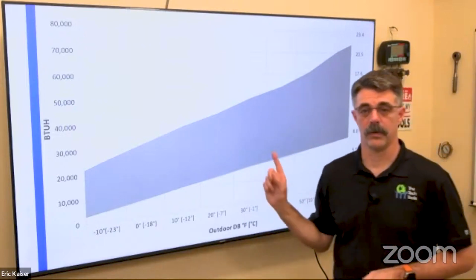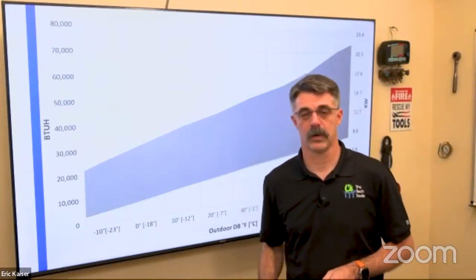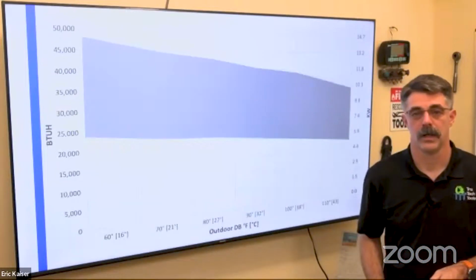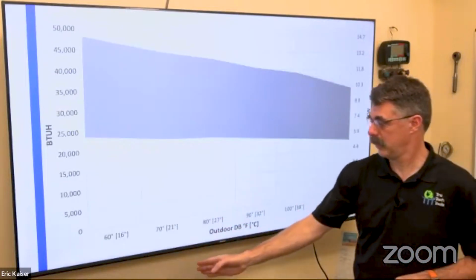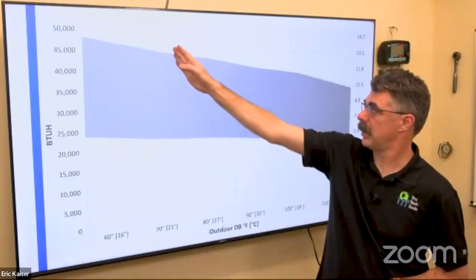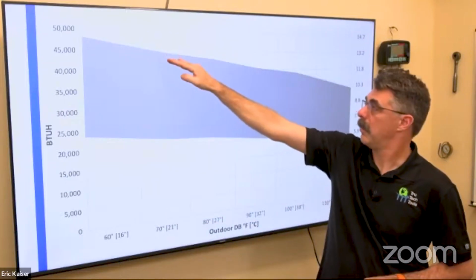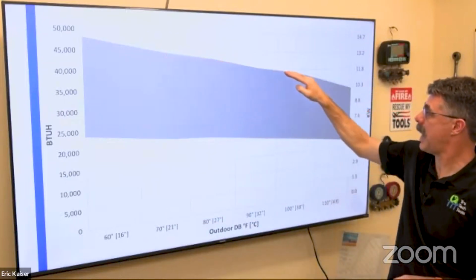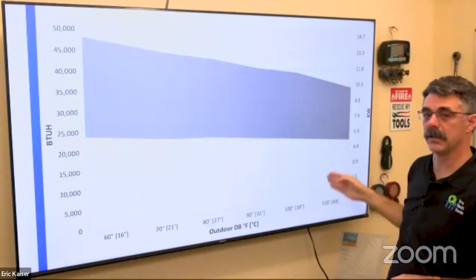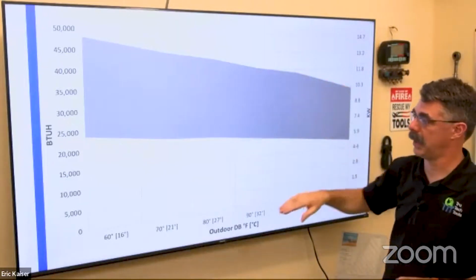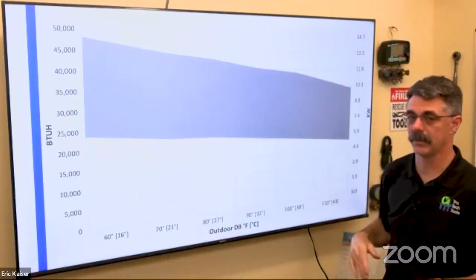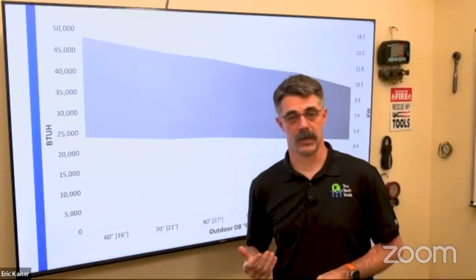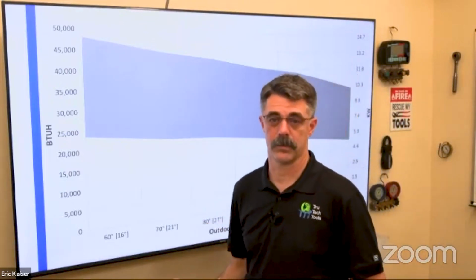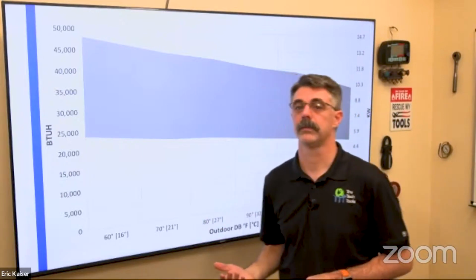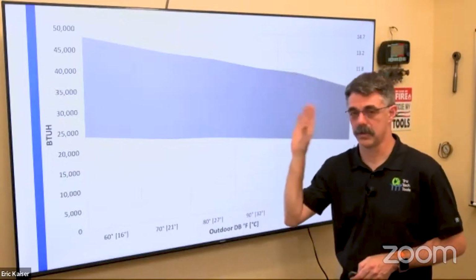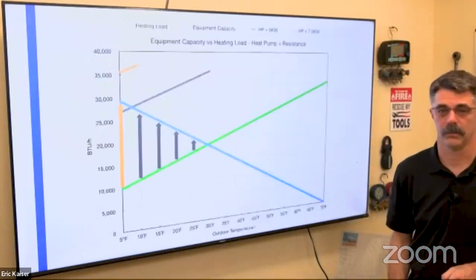And just so you know, this happens to be the heating performance curve of a unit, right? It does the exact same thing in cooling. You'll see this is 70 degrees right here. My maximum tapers off the hotter it gets outside. My capacity actually goes down. Same thing with my minimum capacity. It's going to go down the hotter it gets outside. That's how refrigerant-based units work, right? It's just showing you what it does on the cooling side as well.